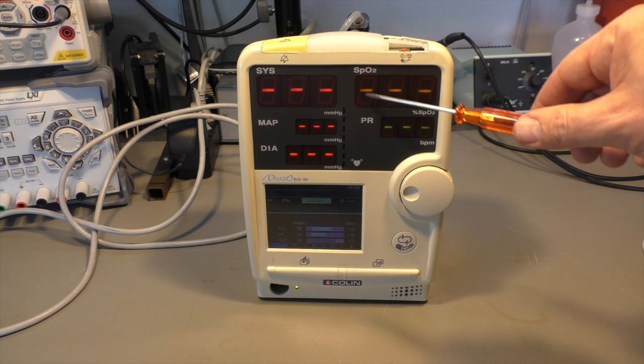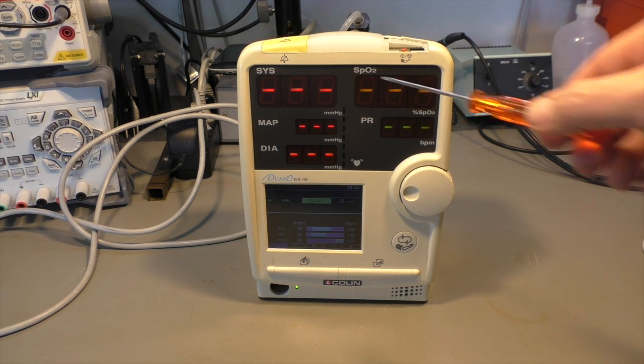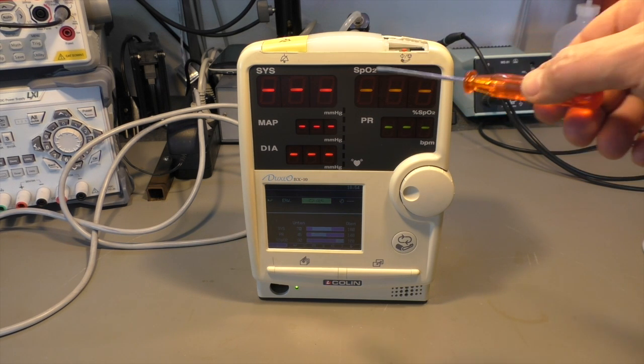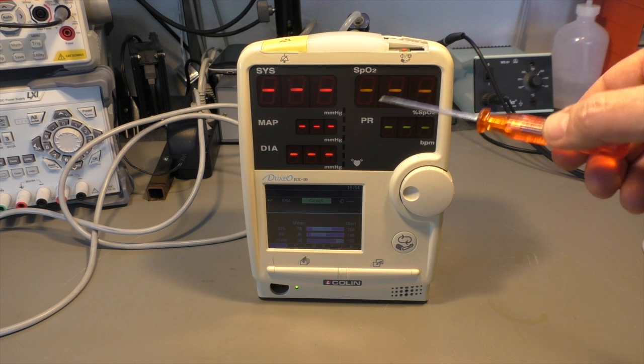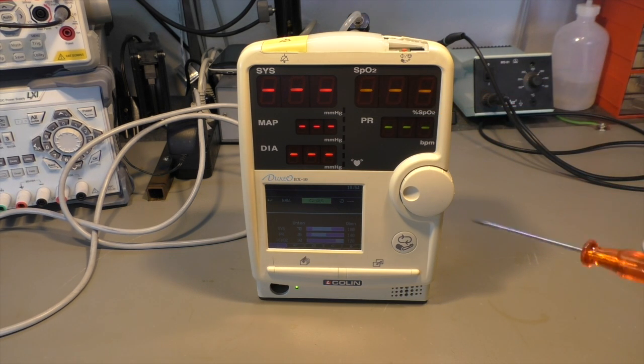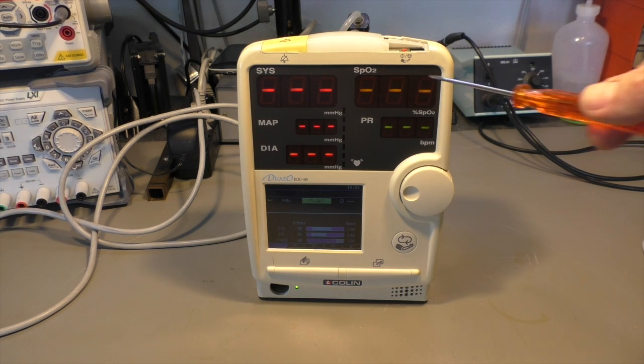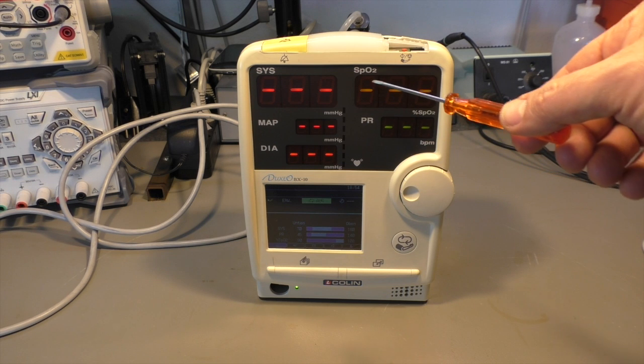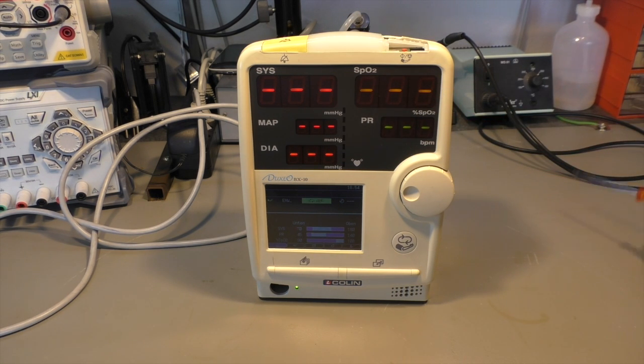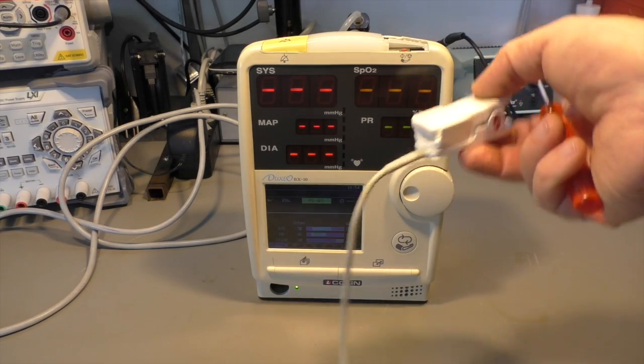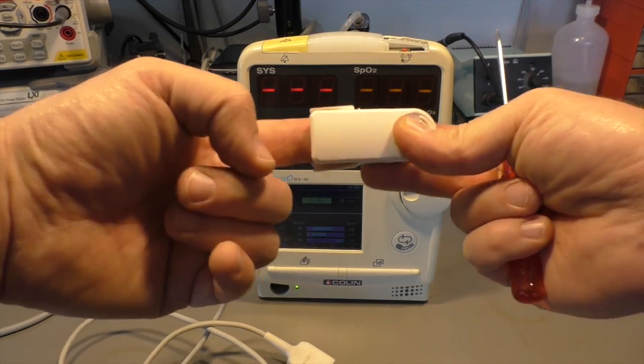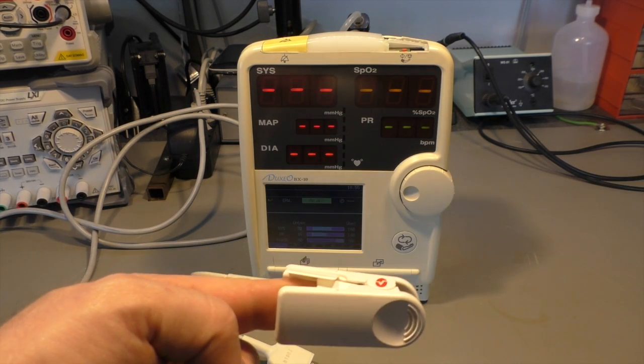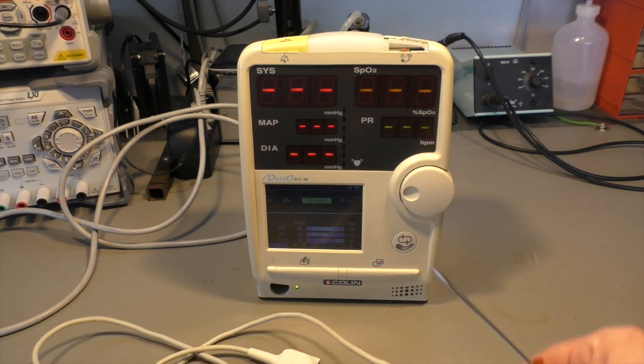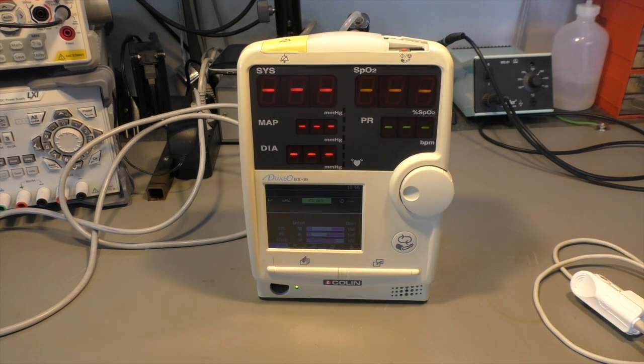On the right side we have SPO2, that means it's the saturation of oxygen in the blood. So an optimal value is 99 or 100%. Then your blood is completely saturated with oxygen. The P here stands for pulse oxy measurement. I hope I pronounced that correctly. It basically means you get a sensor like this, where you stick your finger in, and then it shoots some different wavelengths of red light through your finger. And from the absorption of certain wavelengths, you can determine how much oxygen is in your blood.